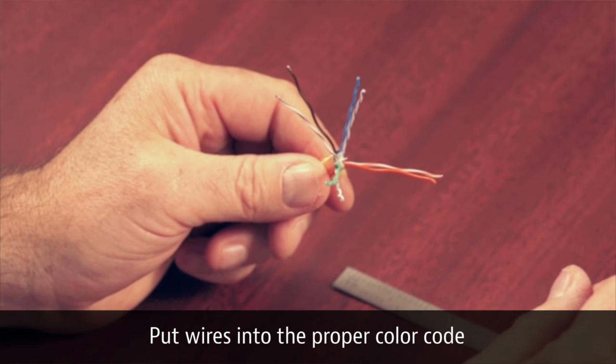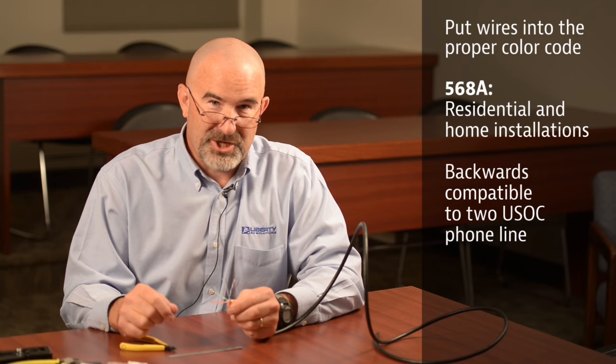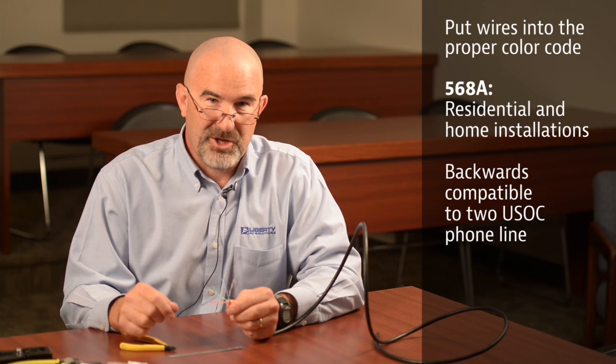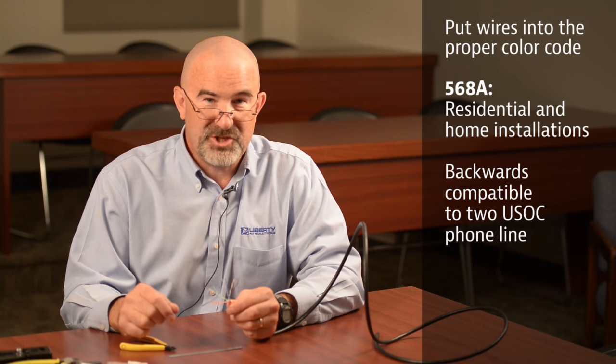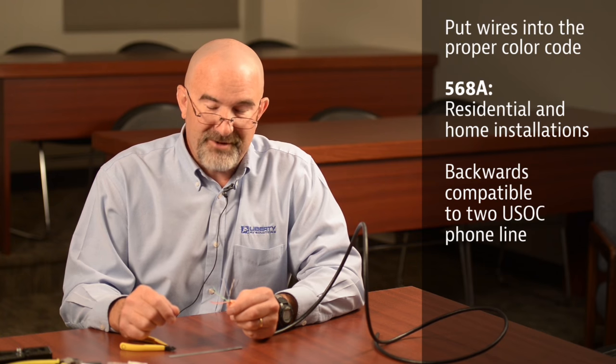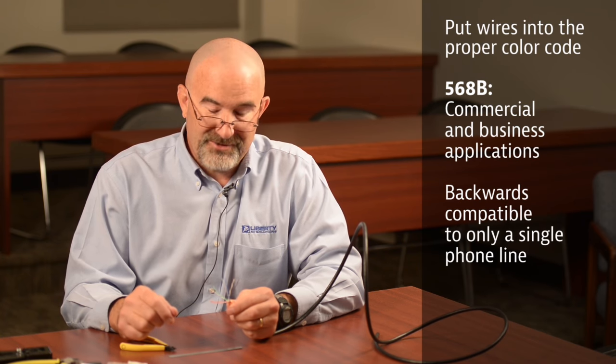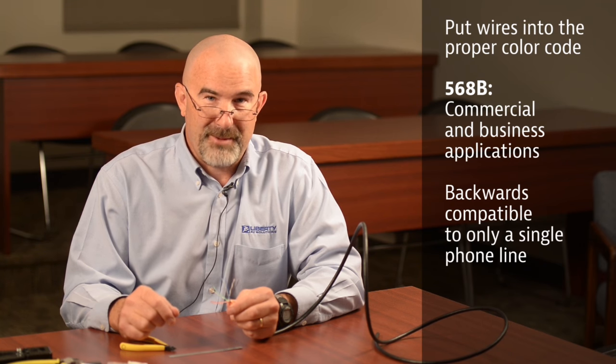Once you have these conductors straightened out, the next step is to put them in the proper color code. We're going to use 568B for our color code. 568A is generally used in residential type applications or home installations because it's forward or backwards compatible to the USOC two phone lines. 568B is only backwards compatible to a single phone line, so it's used primarily in businesses and commercial type applications.